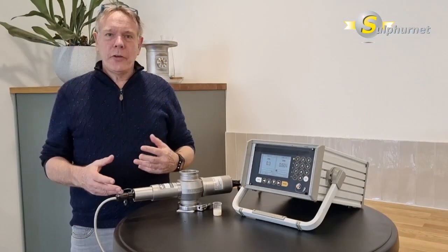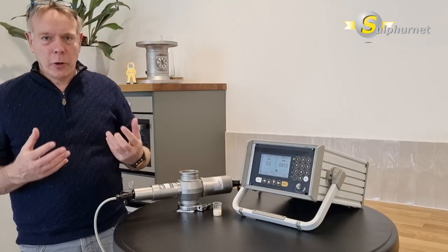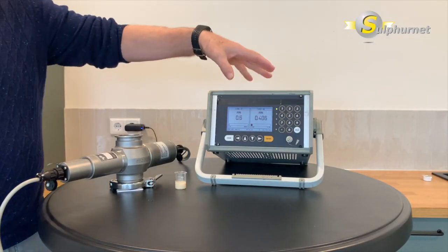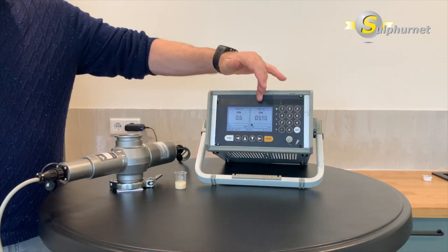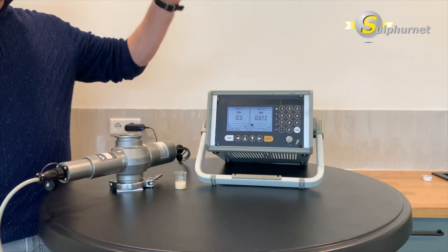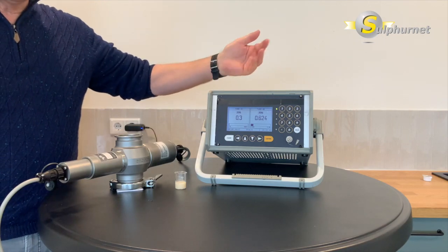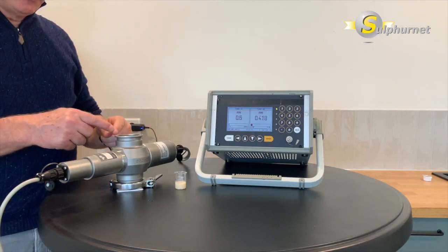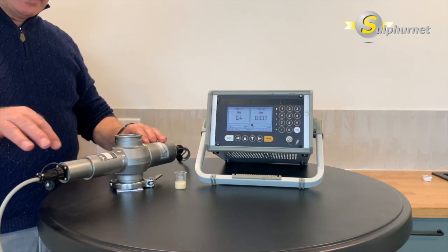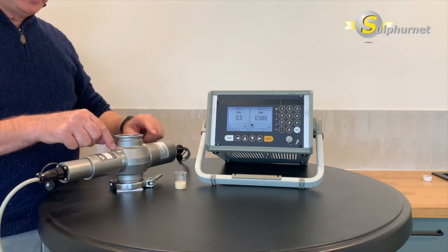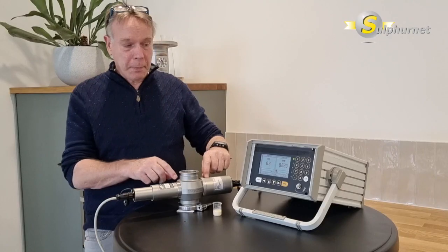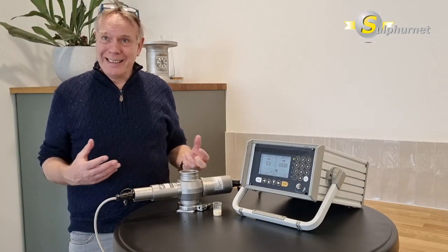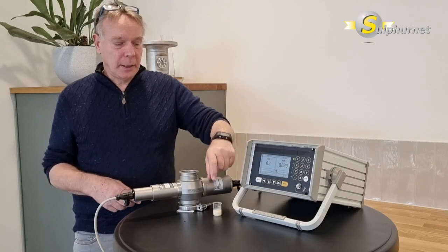Thank you very much. We set up a small demonstration to show how sensitive this detector is. And here you see the measuring device giving the numbers in ppm. The second cell is for a second output where you can measure higher or lower, or you can put a second system on that. Here we have the cell. It's now filled with water. From this side we have the light scattering into the water, and here we have the measuring cell. As you can see, the ppm level is only 0.3 ppm because it's clear water in the cell.